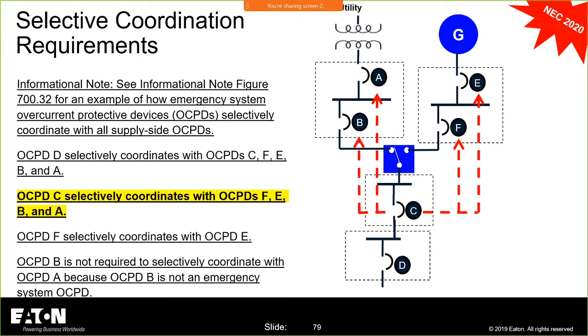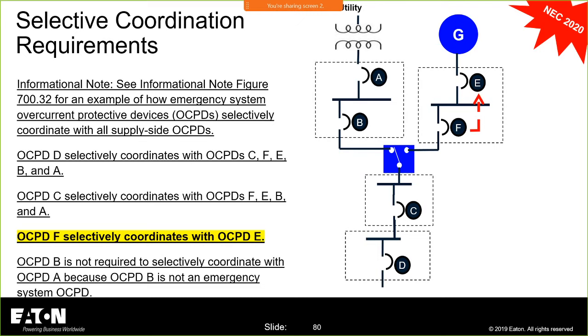And you're always using the maximum available fault current, whether it be from the utility or the generator. Based upon the definition, you can't use the fault current from the generator for these evaluations unless it is greater than what the utility can provide. So, finally, the only other two devices on the emergency side are F and E, and they do have to coordinate with each other. Now, those two devices are only going to see the fault current from the generator. So they don't have to selectively coordinate to what's necessarily coming from the utility if that's greater. You would only have to selectively coordinate the devices E and F with the fault current that's available from the generator.